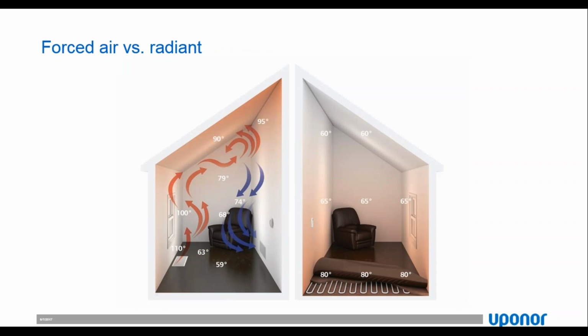Now let's talk about the differences between forced air and radiant as ways to replace heat. Forced air uses heated air as a convection form of heating. It comes into a room, and since hot air rises, it rises toward the ceiling while cold air settles down to the floor. This creates a circulation path, and you can see from the drawing there's quite a variety of temperature from floor to ceiling, which is one of the temperature differences we're talking about.